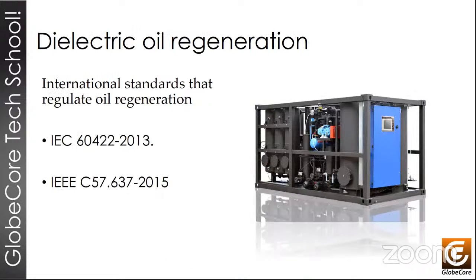There are fairly well-known standards, the IEC 60422-2013 and IEEE C57.637-2015. They describe the use of Fuller's earth and other processes for oil regeneration. These processes take a long time. Therefore, they're performed on live equipment. So oil is regenerated while the transformer is still online and connected to the grid.